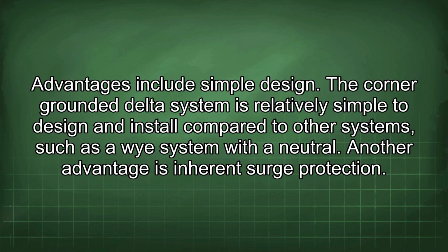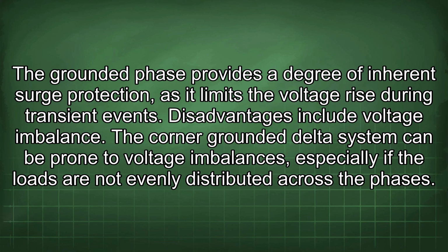Advantages include simple design. The corner-grounded delta system is relatively simple to design and install compared to other systems, such as a Y system with a neutral. Another advantage is inherent surge protection. The grounded phase provides a degree of inherent surge protection, as it limits the voltage rise during transient events.